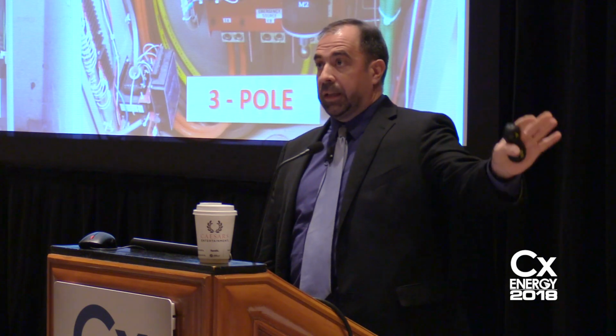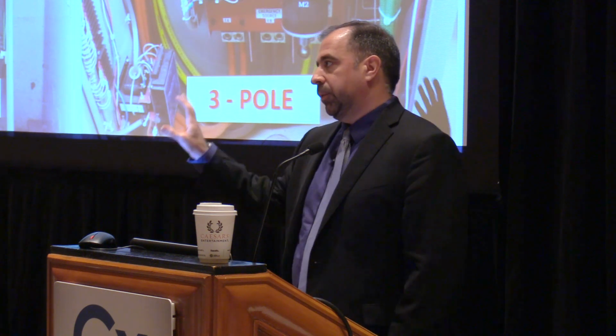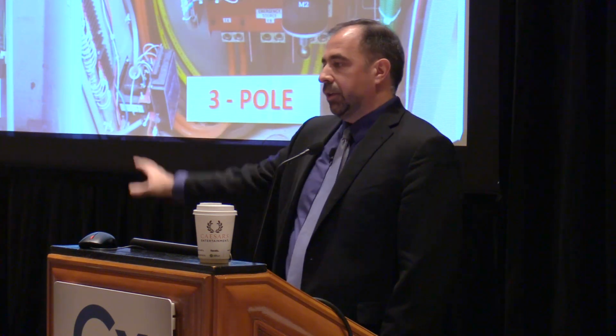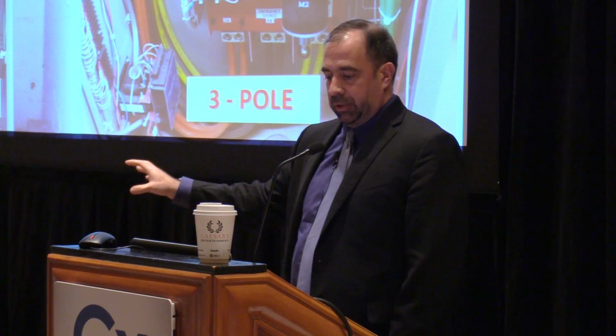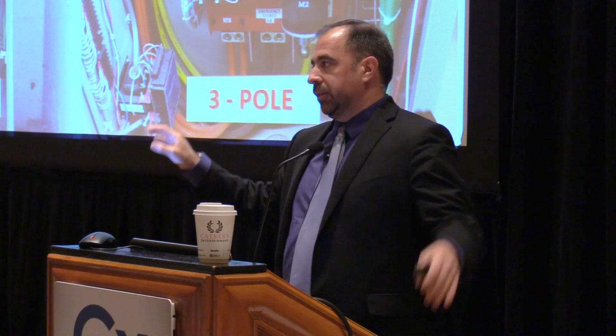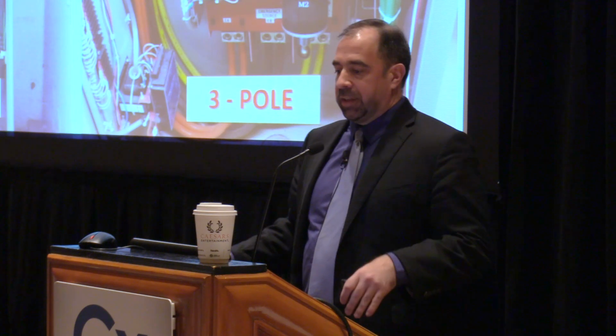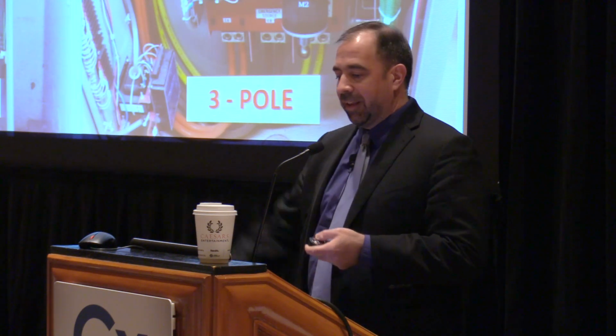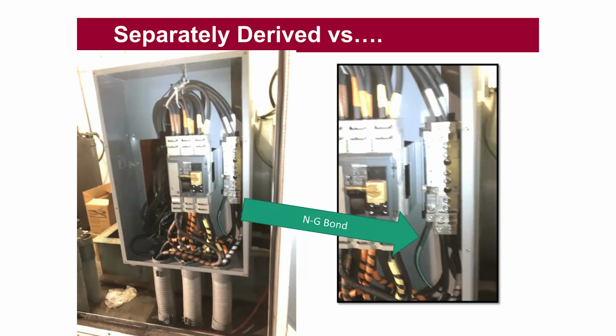With separately derived systems, we're always bonding the neutral and the ground at the utility service. So the real question is, do we bond them together at the generator, at the EPS service too? If we do, then we've separately derived a ground at the generator. If we haven't, then it's not separately derived. See, I can even hear that it's complicated in my head as I say it, the words coming out of my mouth.